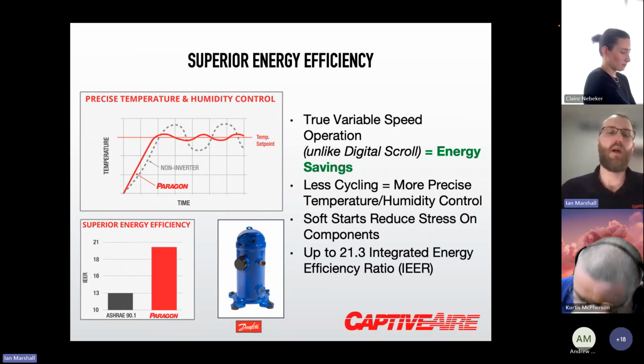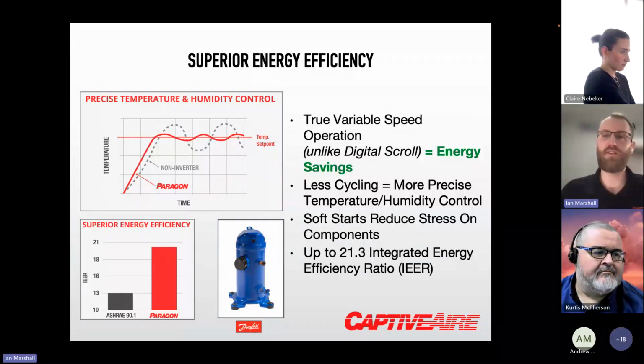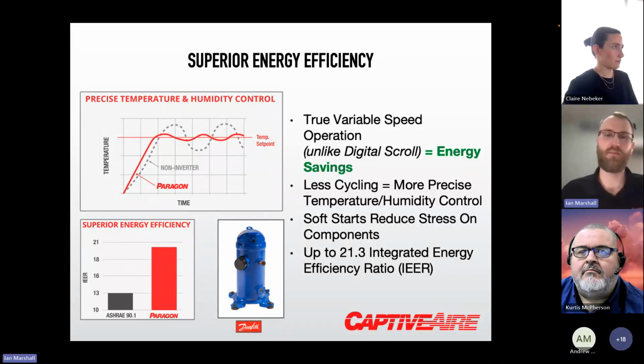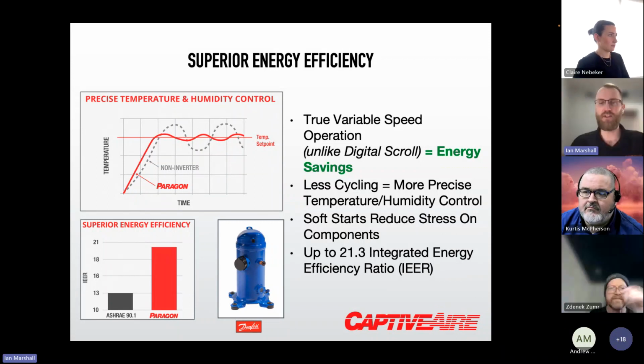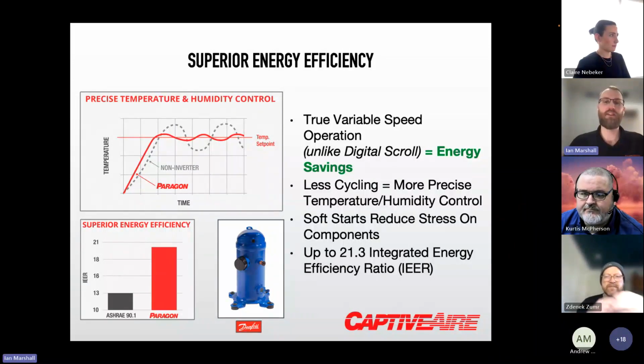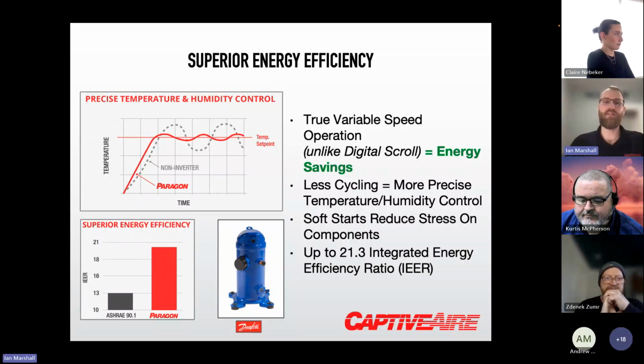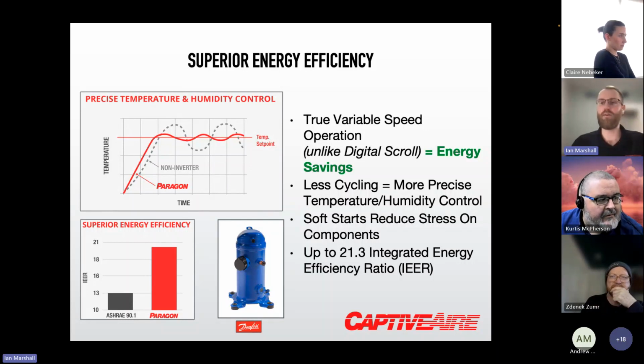So a lot of manufacturers have a digital scroll compressor option, and digital scroll compressors do have some capacity modulation, which comes from separation of the scrolls. Whereas the inverter compressor doesn't separate the scrolls, it just physically slows the speed down with the VFD. So you get the energy savings, which results in less cycling, which results in more precise temperature and humidity control, soft starts on the components, that kind of thing, which gives us up to a 21.3 IEER rating, which is one of the highest in the industry for this type of equipment because of this.